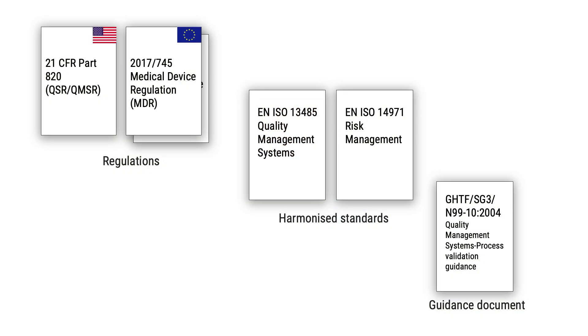These regulations and standards tell us that we have to perform process validation, but they don't really provide much information on how to do it. Fortunately, there is a useful guidance document available on how to perform process validation: the GHTF SG3 N99-10-2004 Quality Management System Process Validation Guidance. I will refer to this as the GHTF guidance, and this course is well aligned with that guidance document.